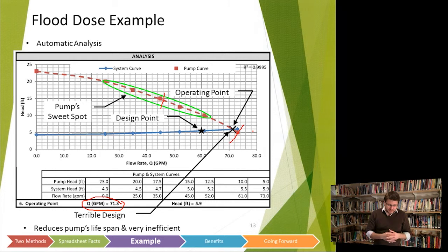From this manufacturer, Zoeller, they actually don't publish their efficiencies, but I would guess there's maybe a 10 to 20% difference in efficiency between the middle of the pump curve and this extreme edge. So over time, let's say you had a pump in a homeowner's property for 10 years or so, the amount of energy they're using is quite a bit more when it operates outside of its sweet spot, that middle half, middle third. Another problem about operating in the extremities is that it reduces the pump's lifespan, the longevity of the pump.